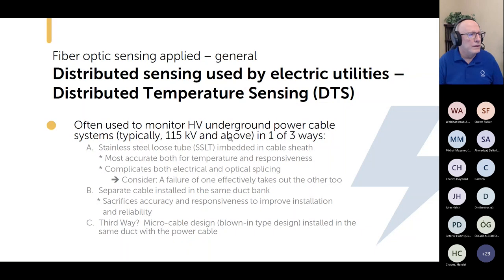So if you have an important 69 kV transmission line or even a sub-transmission line, 35 kV or whatever, you could be using DTS today to monitor the condition of those circuits. And you could do more, as we'll see in just a minute. But basically, the implementation of this is one of three ways. The two most common are to use a stainless steel tube embedded in the cable sheath. And that's very accurate for temperature and responsiveness, but it complicates the splicing, both the electrical splicing, keeping the conductivity of the conductor part of the cable going, and the optical splicing that's required.